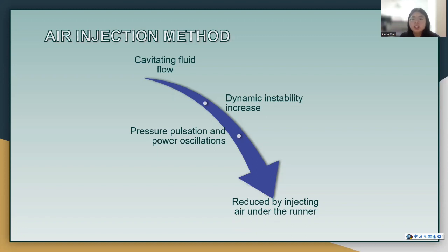In this measure, pressurized air is injected into the horizontal plane of the runner center line at the discharge. The air flow through all the tubes is integrated into each injection point with constant pressure and constant discharge. This technique has been shown to significantly reduce pressure force amplitudes under both part load and full load operating conditions.